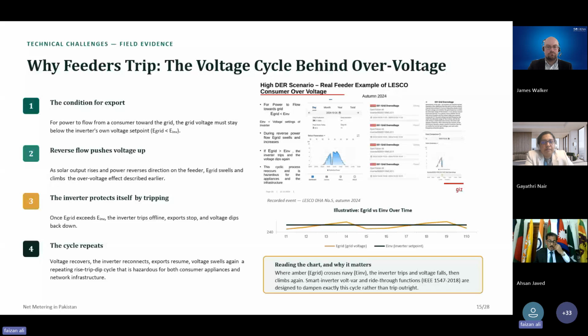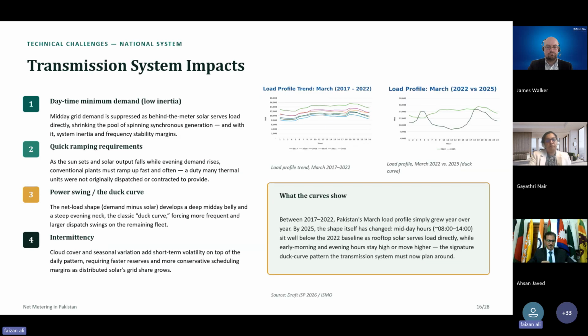So these settings are not catered for and not activated, and the inverters just start to supply on unity power factor. Unfortunately, this is what causes overvoltage of the grid. Now, that is the local challenge.